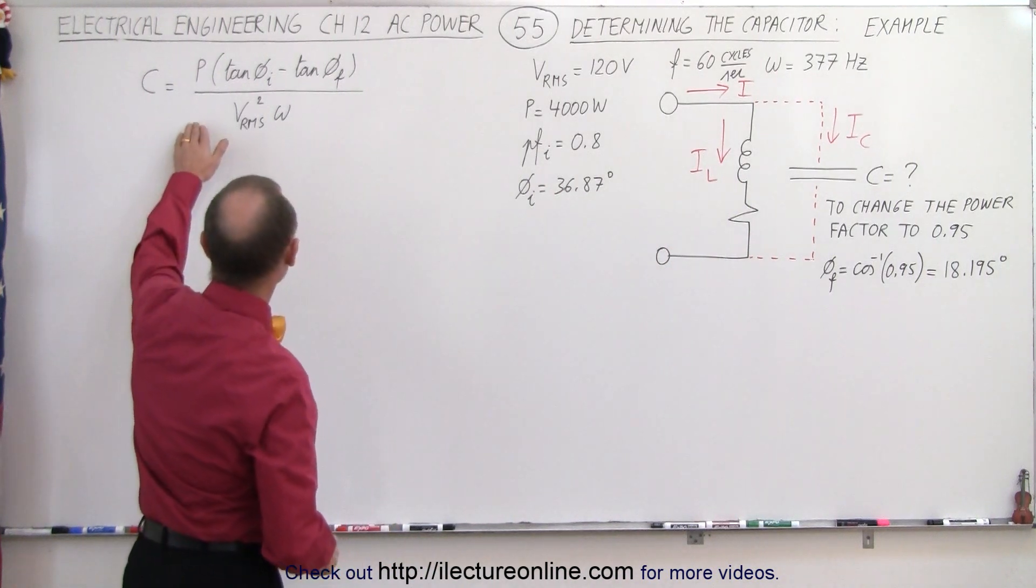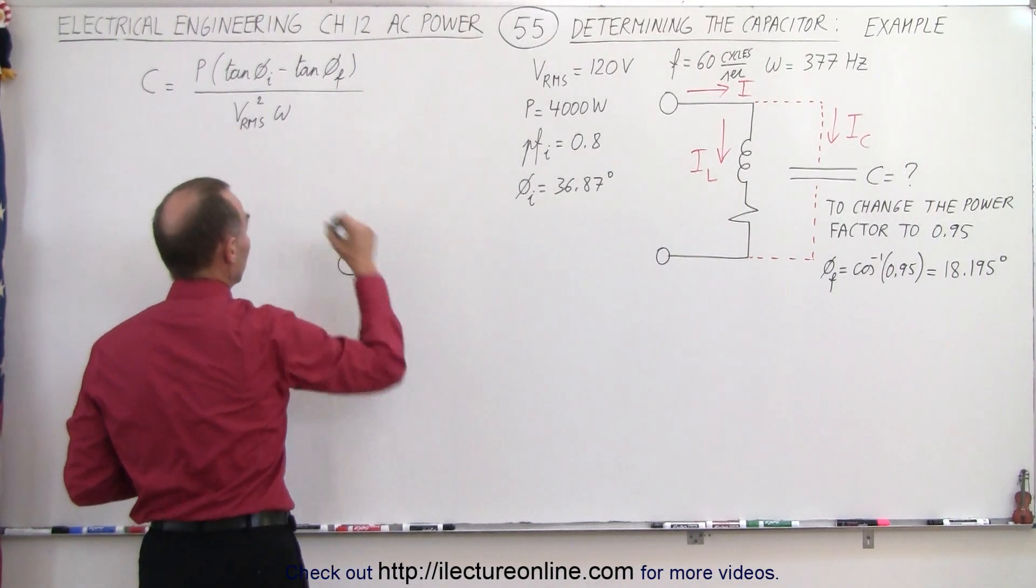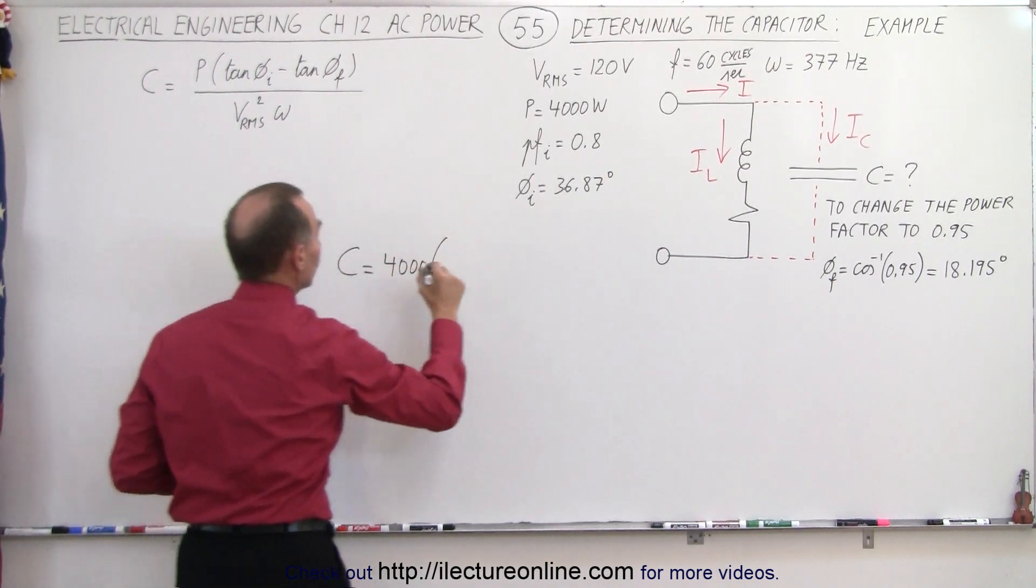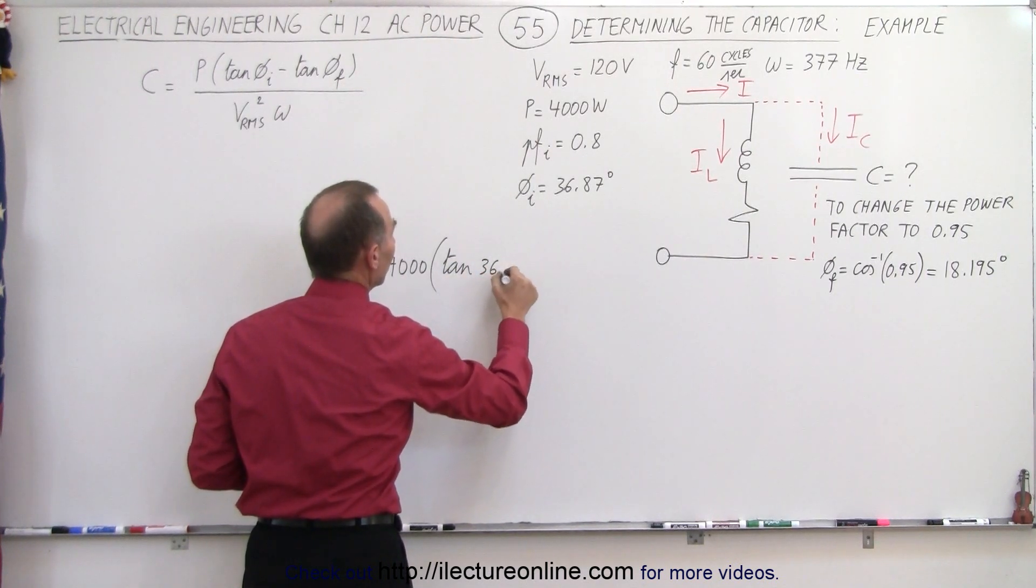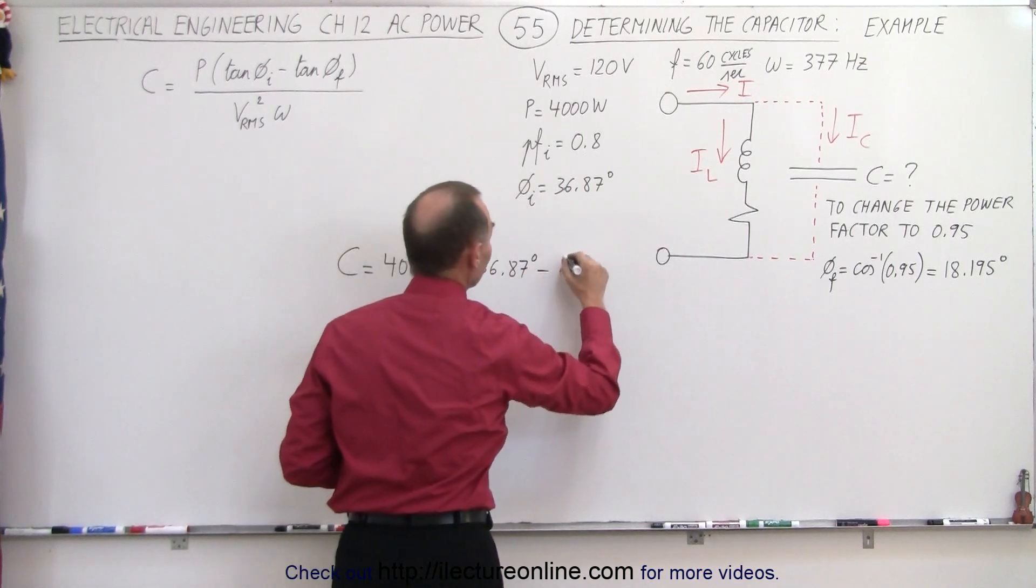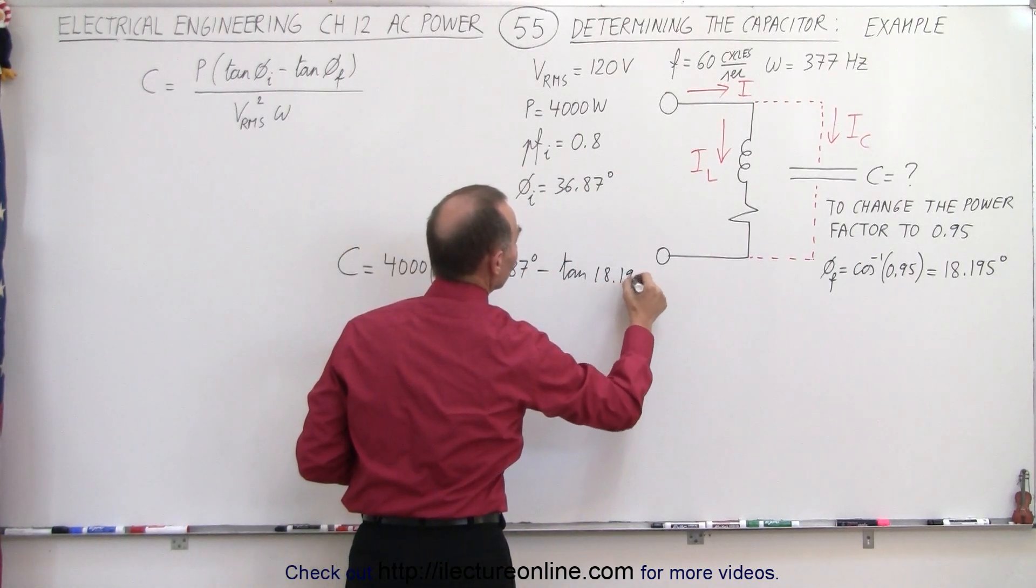So now using this equation right here, we can see that the capacitor is equal to the power, which is 4000 watts, multiplied times the tangent of the initial phase angle, so the tangent of 36.87 degrees, minus the tangent of the final phase angle, tangent of 18.195 degrees.